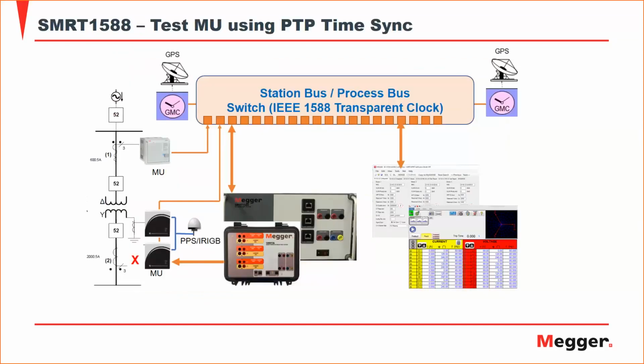This is maybe a quick slide of where this unit fits. It fits mainly in the digital world, but works hand in hand with the FREJA 500 or SMRT units that we supply for secondary injection kits. So the SMRT or FREJA 500 will inject before the merging units like a normal conventional CT, while the SVGS or Smart 1588 will be injecting directly in the switch or your process bus network.